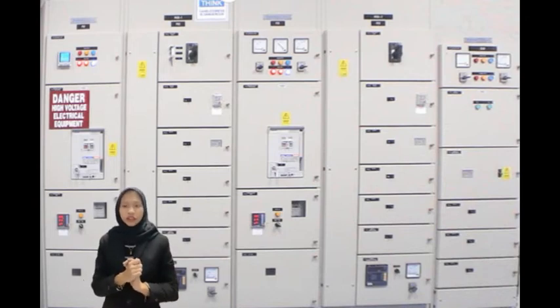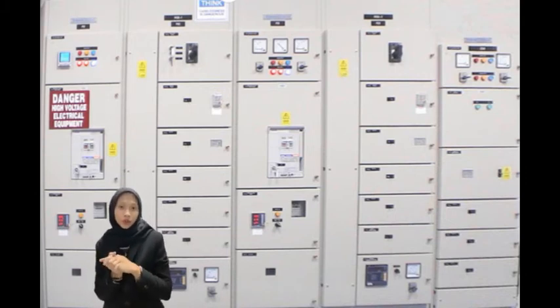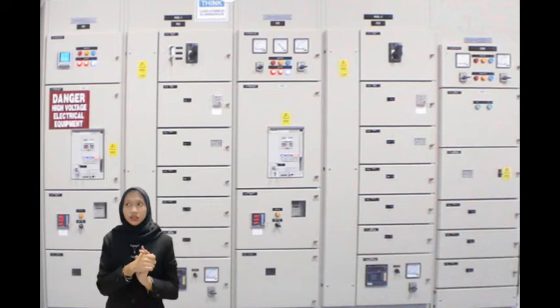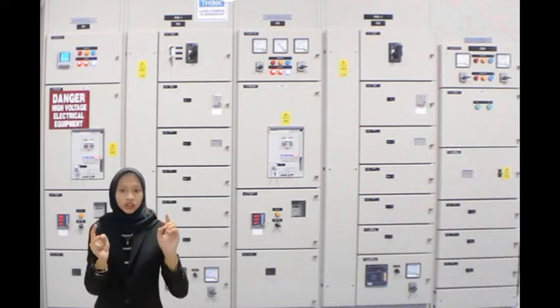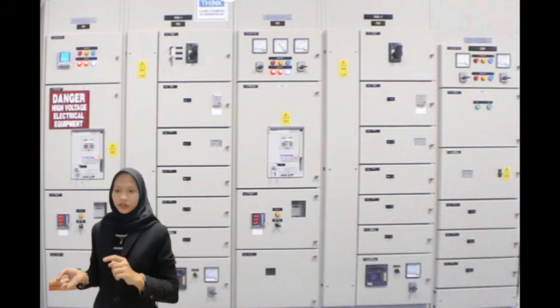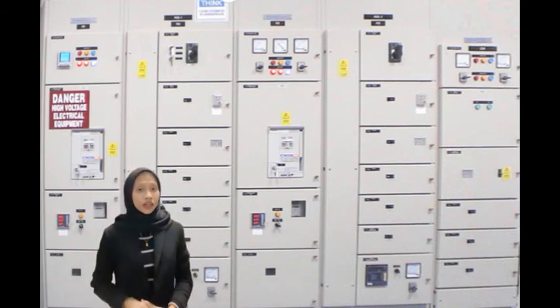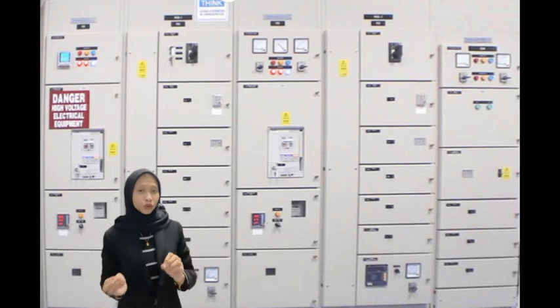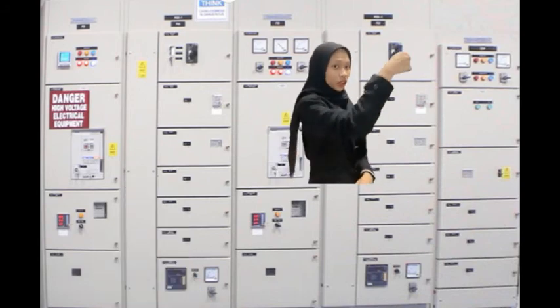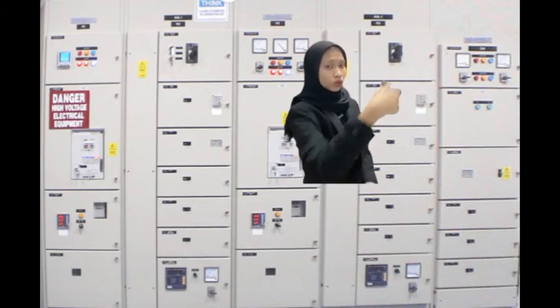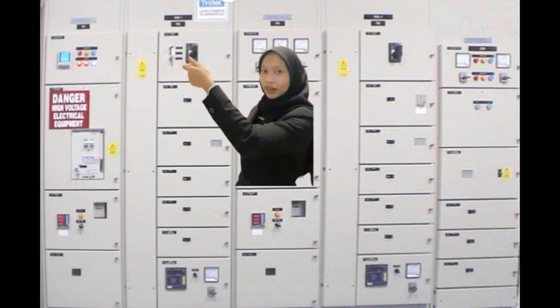It depends on the coupling which isolator to turn on first, isolator 1 or isolator 2. It's either 1 feeds to 2 or 2 feeds to 1. So for this case, MSB2 feeds to MSB1. So we need to turn on the isolator nearest to the supply, which is from up to the lower. So we need to turn on the isolator C2 at MSB2, and then turn on the C1 isolator at MSB1.